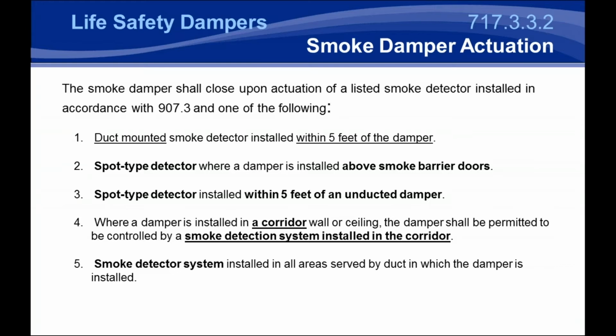Because of that, and because smoke detectors can be installed within 5 feet of an unducted damper or 5 feet of a smoke barrier in a damper, or a damper installed in a smoke barrier, we typically recommend, if you do buy smoke detectors, buy them as loose for field mounting. Typically, when you get to a job site, there are a lot of trades vying for the same spot within limited space in these buildings, and because of that and the flexibility of being able to install that smoke detector within 5 feet of the damper, we do recommend field install, because then you can wire it back into your damper or your smoke control system and still have the flexibility to not compete with trades.